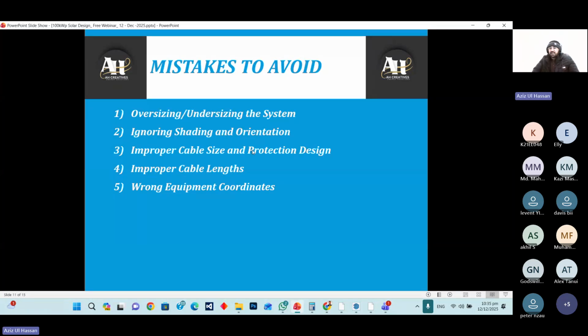Then mistakes to avoid, like oversizing, undersizing the systems, and ignoring the shading and orientation. Oversizing and undersizing means that when we are doing the cable sizing, most of the time people oversize or undersize the cables. Both are mistakes. We have to optimize that design. Ignoring shading and orientation means that if any object is present which causes a shadow on our solar power plant, we have to avoid that area and leave that space for shading purposes.